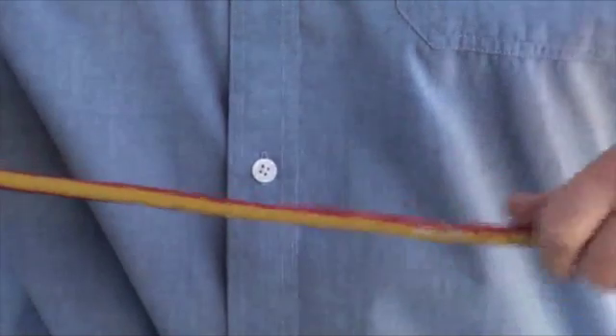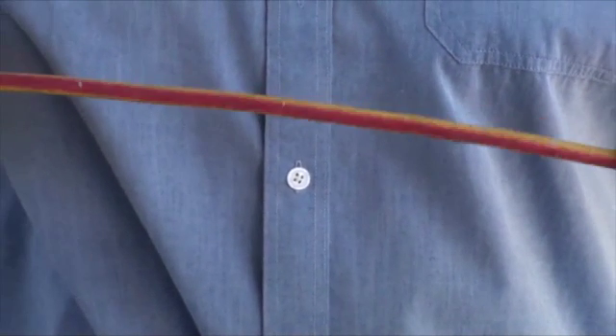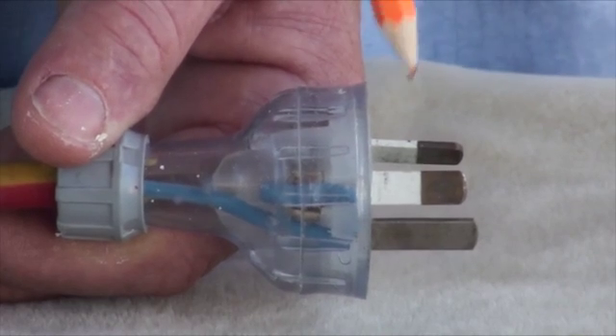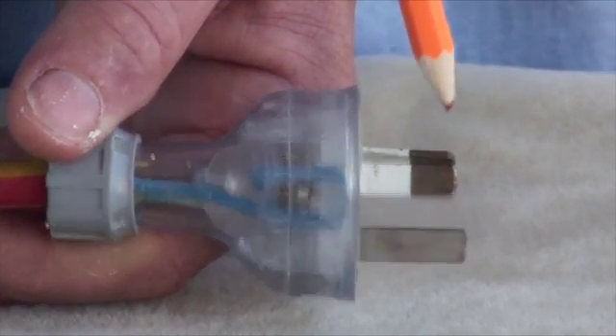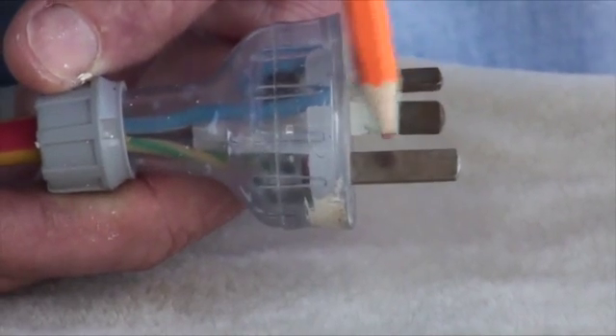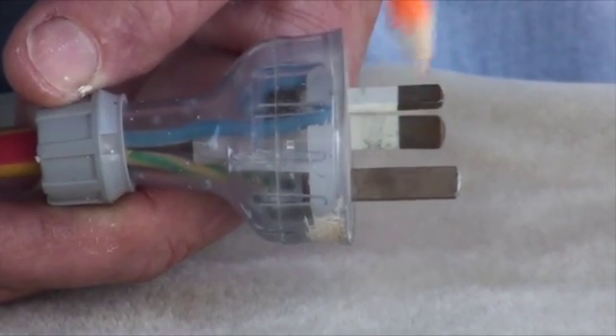It's a good idea to purchase heavy duty cords that will handle more wear and tear due to the thicker outer insulation. When inspecting the male end of the cord or tool, ensure that the prongs are straight and that they have a fine coating of insulation over the two prongs — active and neutral.